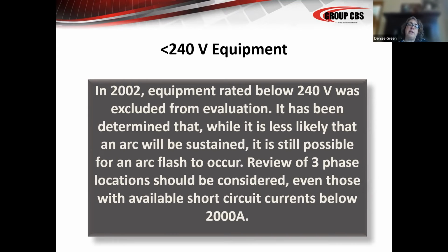There was some calculation being done for currents over 2000 amps at a 240 volt level, but they expanded those calculations in 2018 to capture areas where personnel might be in danger and that were not being considered previously. So that's the first really big change on lower voltage equipment. In your facilities, it's definitely a thing to evaluate. If you have very low amperage breakers at 220 volts, 30 amps, 40 amps, chances are your arc flash is not going to exceed anything that is a concern other than normal PPE. But when you start getting into larger amperage breakers at that lower voltage rate, you really might consider having that calculated to make sure that everyone is protected when they're standing in front of it and operating that equipment.